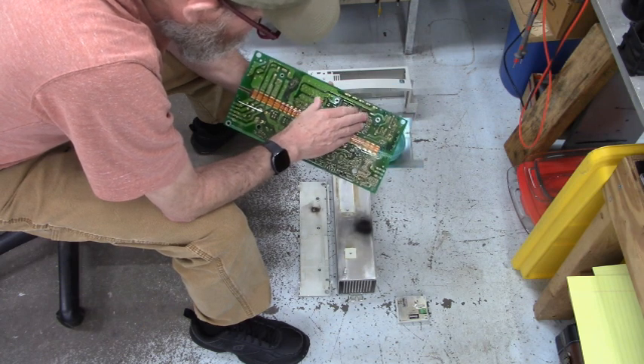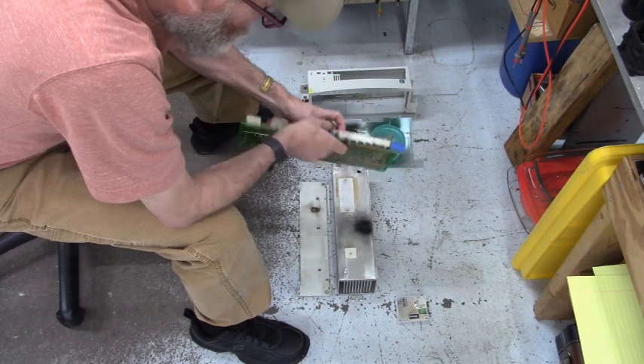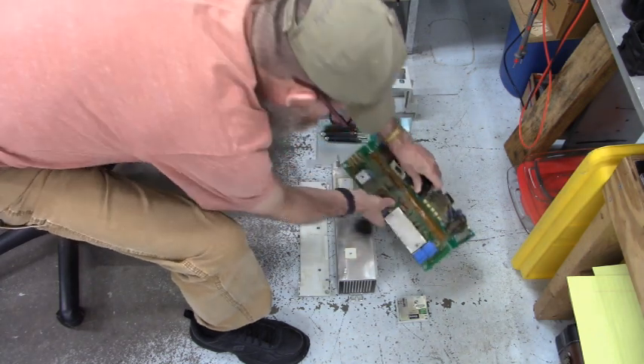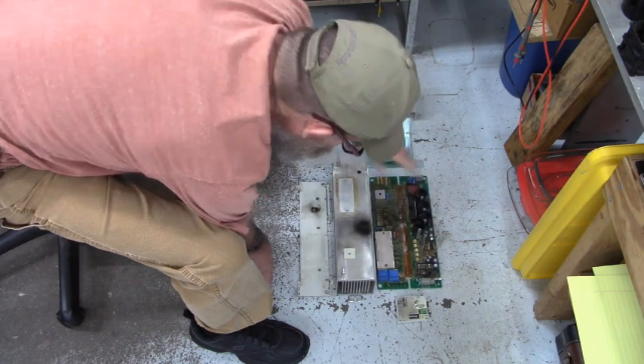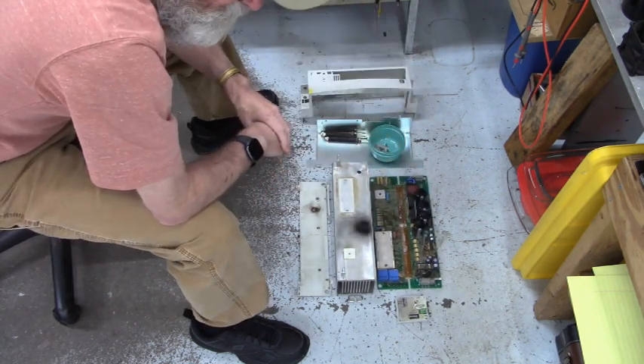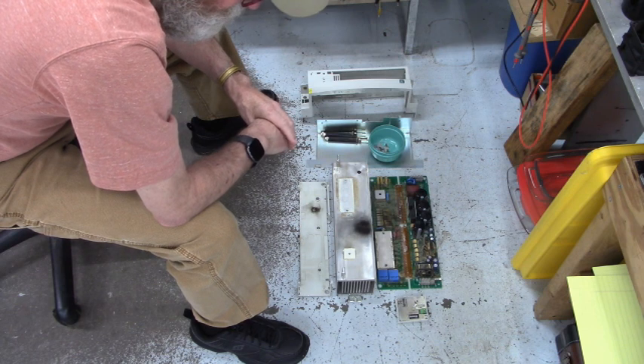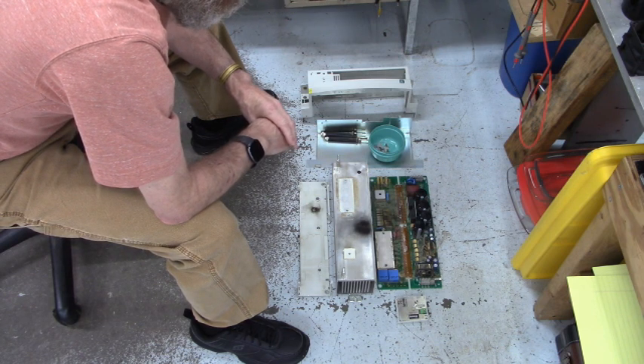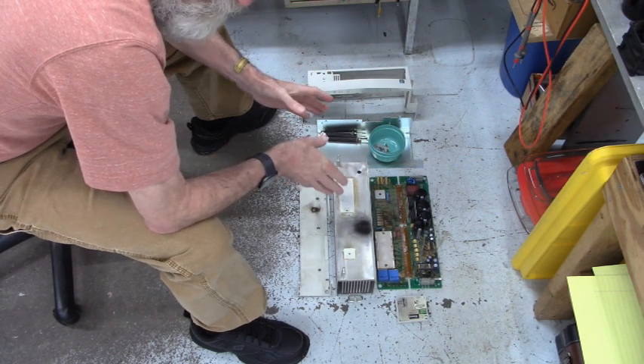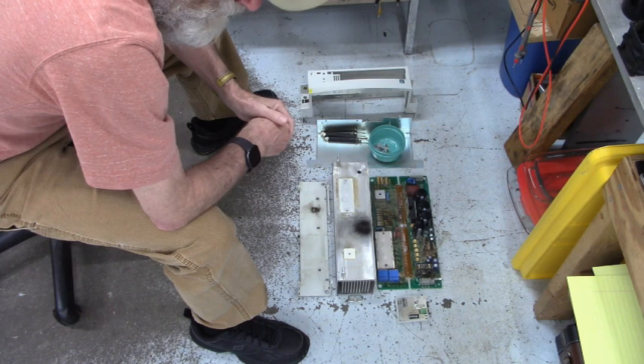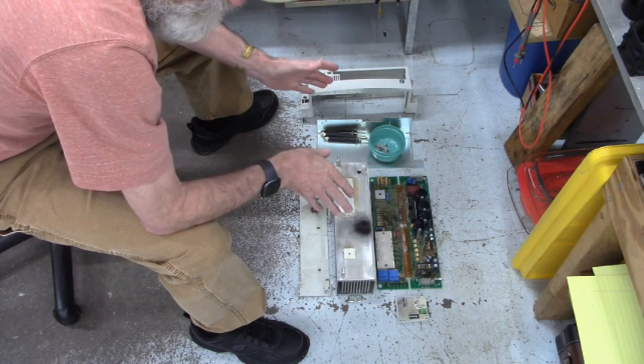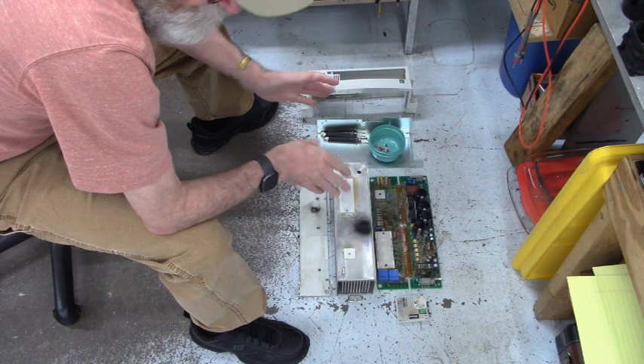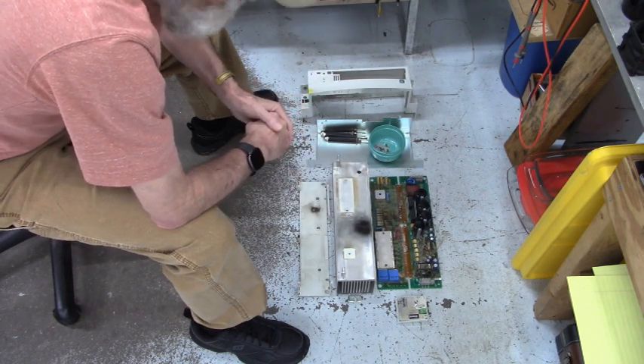This in my opinion is unrepairable. Reason being it's conformally coated and those surface mount devices are very tiny and hard to replace. So if we were to try to repair this power board it might flame out after our repair if I miss an NPN or a PNP transistor in the gate firing channel.